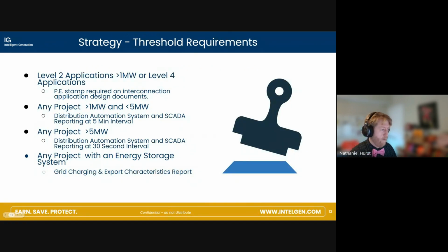So what are some important threshold requirements outside of what the ICC requires? Speaking from ComEd's world, level 2 applications over 1 megawatt and level 4 applications have a variety of design factors that require a PE stamp just to apply for interconnection. This is really important for things like sizing the transformer, sizing wire, overcurrent protection devices, and most importantly, relay and control protection schemes, which are fairly niche, fairly esoteric. It's very important to get an engineer tagged in who can stamp your drawing. They don't necessarily need to be the engineer of record all the way to the end — that will be your electrical or civil engineer — but they need to be somebody who can create a package that can bring in those engineer-of-record partners in the future.